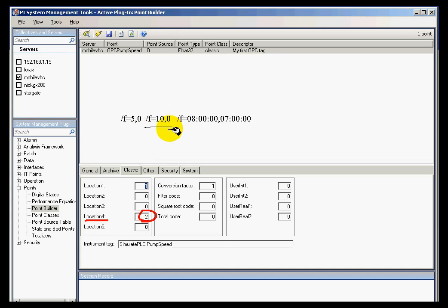This scan class right here is scan class 2. So by choosing a 2 for location code 4, we're mapping that to the second scan class. This particular tag would get 10 second scanning. Now if I wanted a scan class that goes once every 8 hours, with an offset of 7 hours from the beginning of the day, this would go at 7 in the morning, then 3 in the afternoon, and 11 o'clock at night. This would be a 3 in location code 4, because that is the third scan class. So we just count over here: this is scan class 1, this is scan class 2, scan class 3 here.